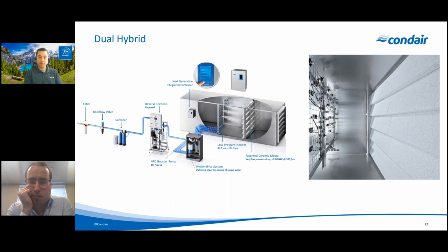So for retrofit applications, this would be a really good product to start looking at if you've got, say, a short absorption manifold or a steam grid inside the air handler that maybe has 4 to 5 feet of install length with that steam grid in there. So really, really good product here to look at for adiabatic retrofit applications inside of an air handler.